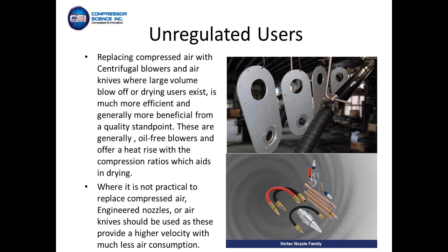But it's the velocity in a lot of these cases which actually does the drying, the impingement velocity on the product or on the surface, as opposed to just smashing it with compressed air. So where it's not practical to look at blowers versus compressed air or change the process somehow, we do look at engineered nozzles, where if you can take that 1/4 inch or 3/8 copper or aluminum tube that you're using for blowing off your product or your process, and you put an engineered nozzle on it, you're actually increasing the velocity with the engineered nozzle, and you can get away with a much lower pressure and a lower consumption of compressed air by hitting it with a higher velocity at a lower pressure, as opposed to just hitting it with 100 psi through an open orifice.